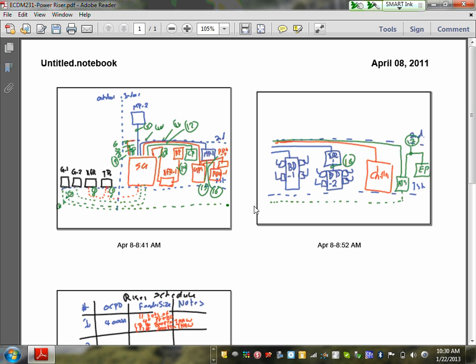And then, some of the generator manufacturers might do a soft load transfer. That's mainly if you're going from utility to gen power, for load preservation or load shed, where you're actually generating with utility, or the utility calls and says you have to get off the grid. At that point, they may just go on the generator, even though utility power is there, because they'll get a better rate from the utility.